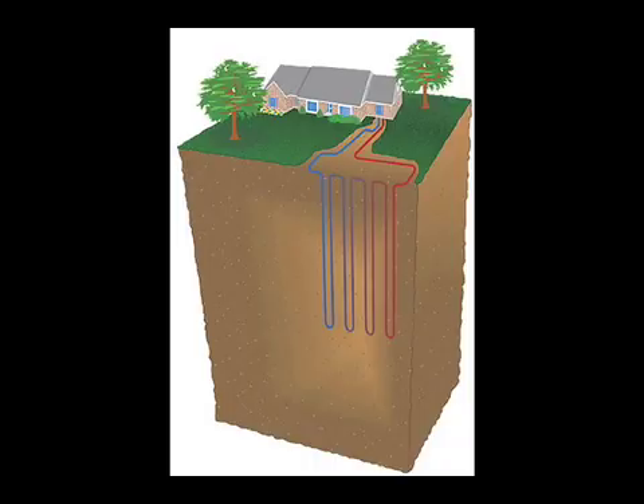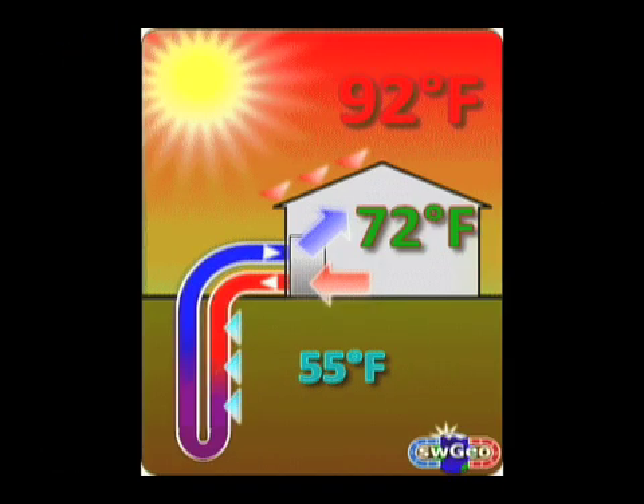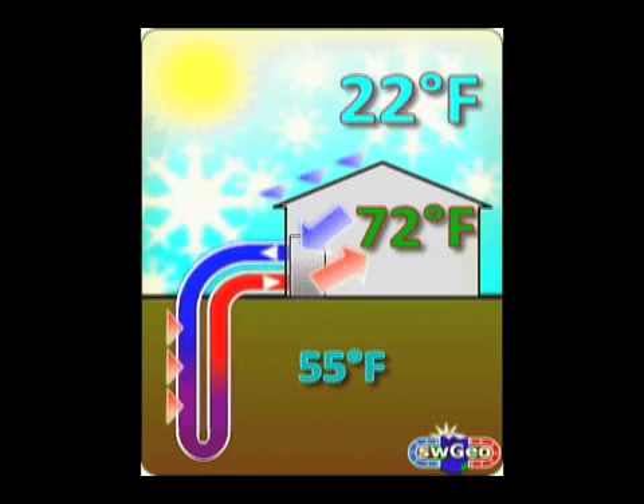The way we do that is we drill holes into the ground — about five-inch holes that go down a couple hundred feet. We put one-inch pipe down; it's a loop that goes down and back, and we circulate about 15 gallons of water a minute. We can heat your house with air, or transform that to hot water and heat your floors with radiant heating.